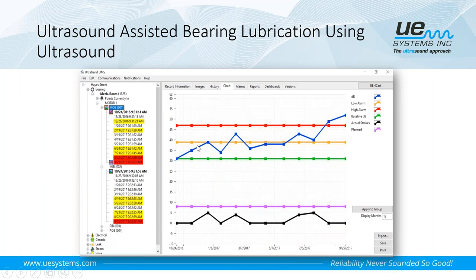Now, a lot of people like to see just simple trends of their data. So you have that ability. If I want to see a trend of this motor one, motor outboard bearing, I just simply click on that motor outboard bearing, click on chart, and we're looking at two things on this chart. In this case, we're using 30 dB as the baseline, and we're plotting our historical readings, and we see the low alarm plotted and the high alarm plotted. So we can see how our decibel level has continued, in this case, to trend upwards.